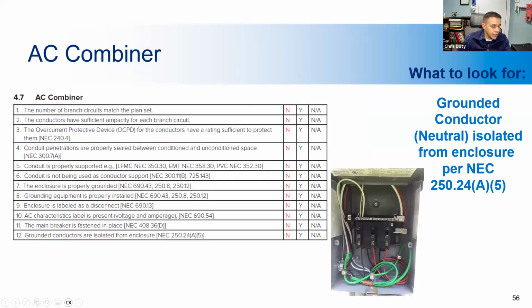All right, so now we're going to look at an AC combiner panel. This is where multiple arrays may be connected to be combined into one single feed before going into the interconnection. It's kind of like a sub panel, but it's slightly different. So not only does the overcurrent protection need to be appropriately sized in here, the enclosure needs to be properly bonded and grounded, and the neutral must be isolated from the enclosure. So you can see here, there's a separate neutral bar, and it's not connected to the enclosure, and the grounding wire, which is the green wire, as you would expect, is connected to the enclosure. So the enclosure is properly bonded and grounded in this system.